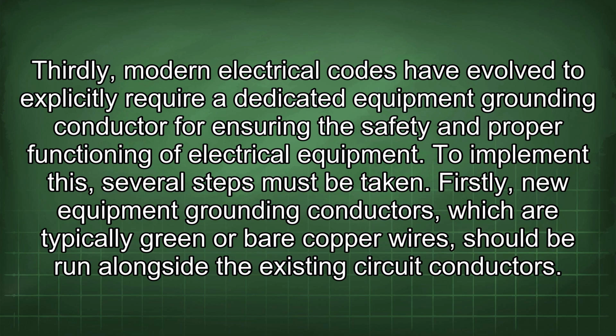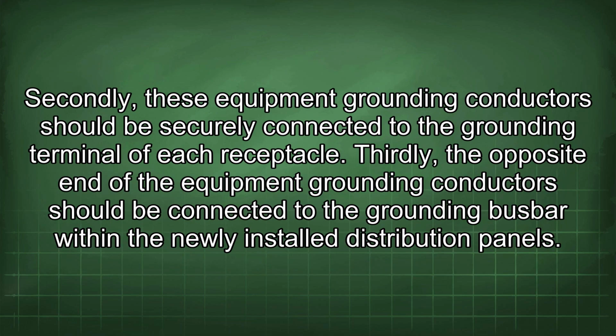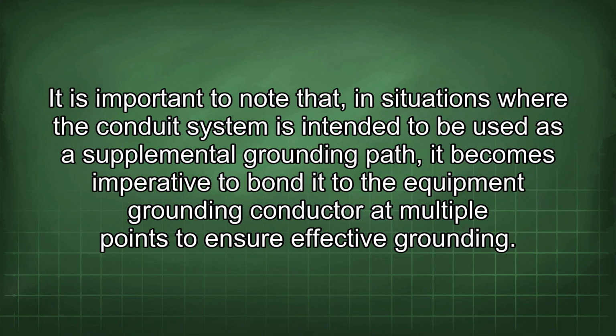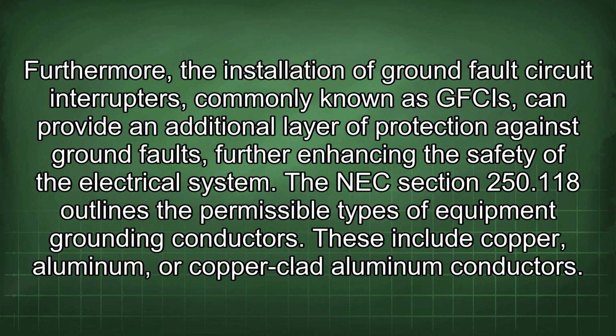To implement this, several steps must be taken. Firstly, new equipment grounding conductors, which are typically green or bare copper wires, should be run alongside the existing circuit conductors. Secondly, these equipment grounding conductors should be securely connected to the grounding terminal of each receptacle. Thirdly, the opposite end of the equipment grounding conductors should be connected to the grounding busbar within the newly installed distribution panels. It is important to note that, in situations where the conduit system is intended to be used as a supplemental grounding path, it becomes imperative to bond it to the equipment grounding conductor at multiple points to ensure effective grounding. Furthermore, the installation of ground fault circuit interrupters, commonly known as GFCIs, can provide an additional layer of protection against ground faults, further enhancing the safety of the electrical system.